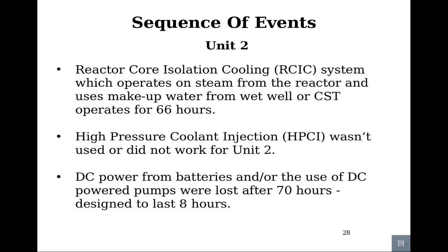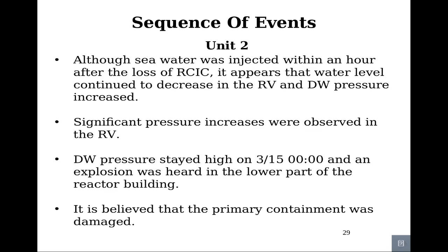Unit 2. The reactor core isolation cooling system, which operates on steam from the reactor and uses makeup water from the wet well or CST, operated for 66 hours. High pressure coolant injection wasn't used or didn't work for Unit 2. DC power from batteries and the use of DC powered pumps were lost after 70 hours. Although seawater was injected within an hour after the loss of RCIC, it appears that water level continued to decrease in the reactor vessel, and dry well pressure increased. Significant pressure increases were observed in the reactor vessel.